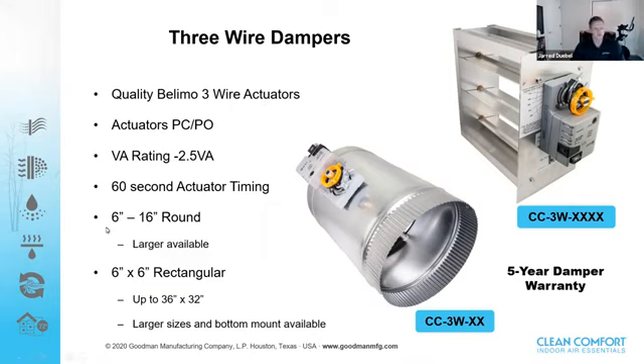Again, from 6-inch to 16-inch round, we can do larger, and then from 6x6 all the way up to 36x32 on the rectangular. So as far as nomenclature, Clean Comfort 3-wire, you're going to have, let's say, a 10x8. That's going to be a side mount damper.